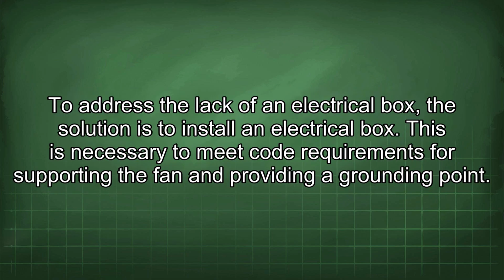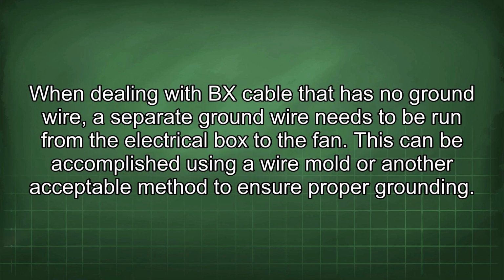To address the lack of an electrical box, the solution is to install an electrical box. This is necessary to meet code requirements for supporting the fan and providing a grounding point. When dealing with BX cable that has no ground wire, a separate ground wire needs to be run from the electrical box to the fan. This can be accomplished using a wire mold or another acceptable method to ensure proper grounding.